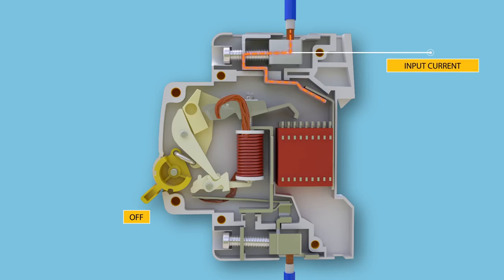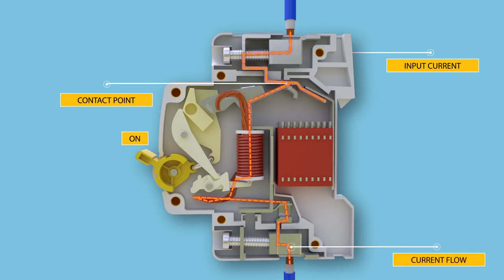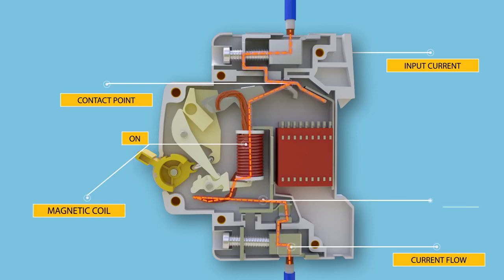Under normal working conditions, the circuit breaker works when we switch the operator manually from position off to position on. The electric current carrying path, as shown in the animation, goes: first the incoming terminal, then the contact point of moving and fixed contacts, then the magnetic coil, then the bimetallic strip, then the outgoing terminal — all arranged in series.